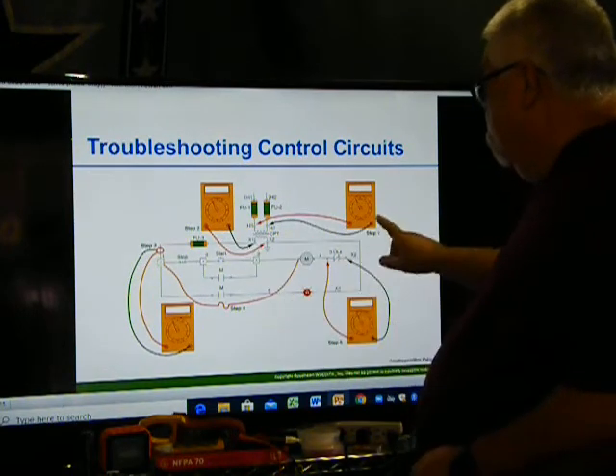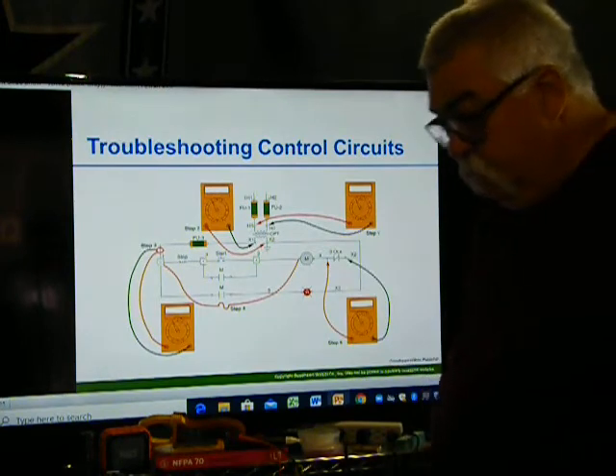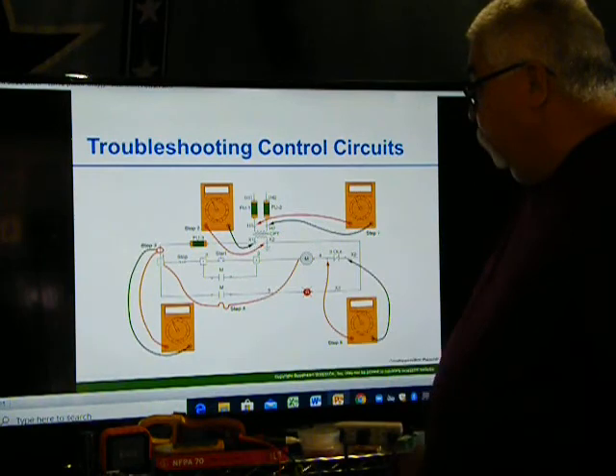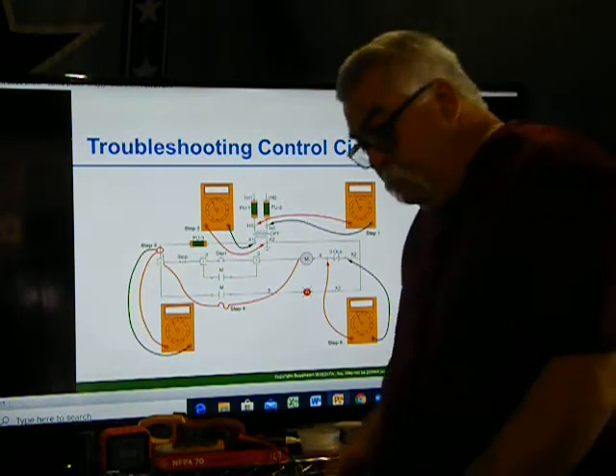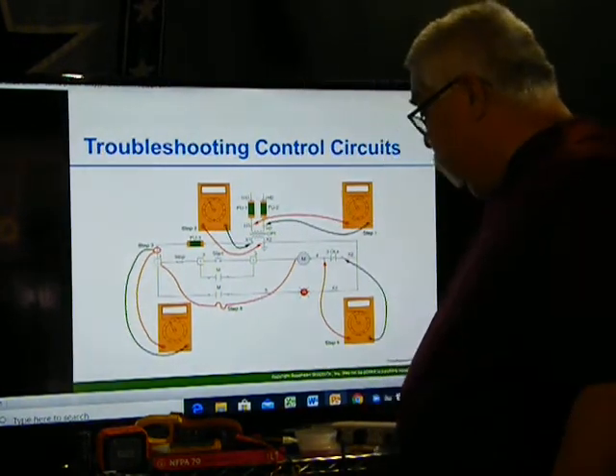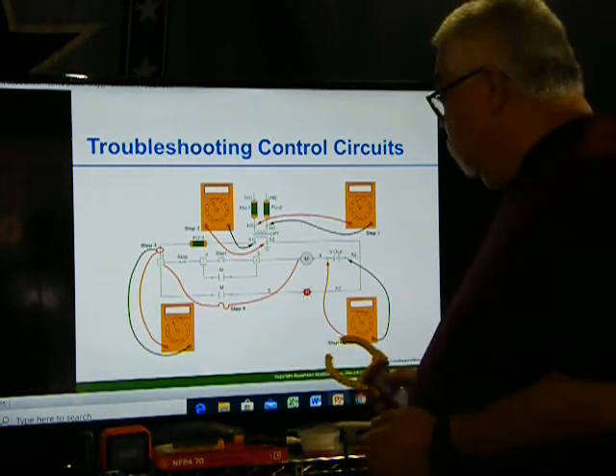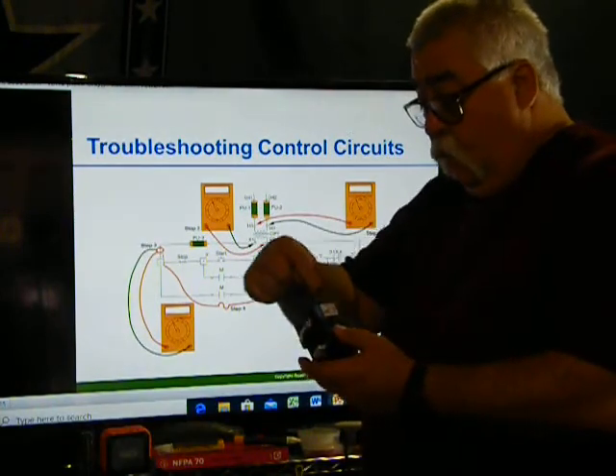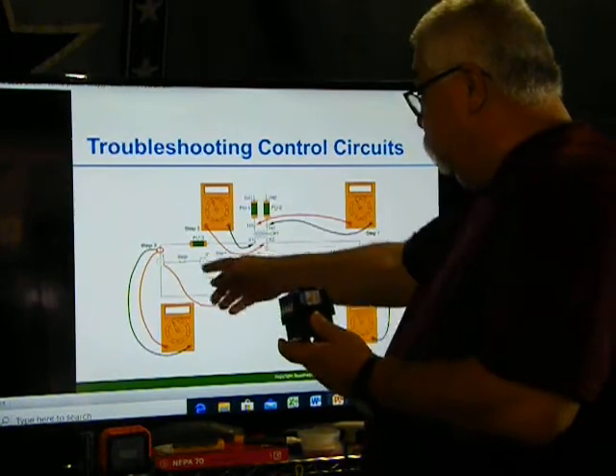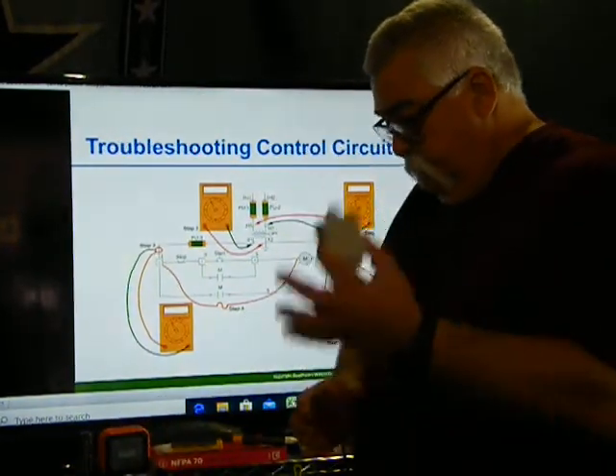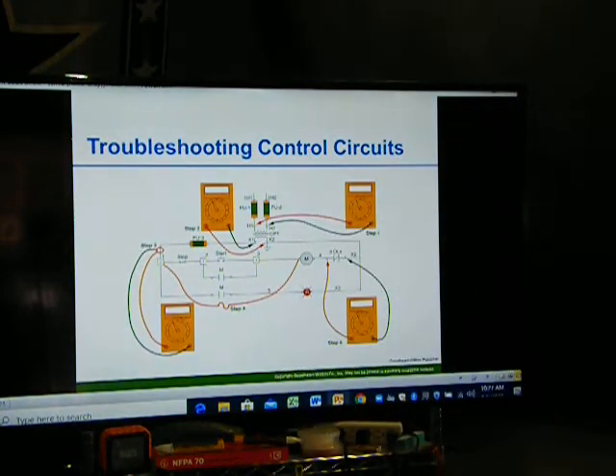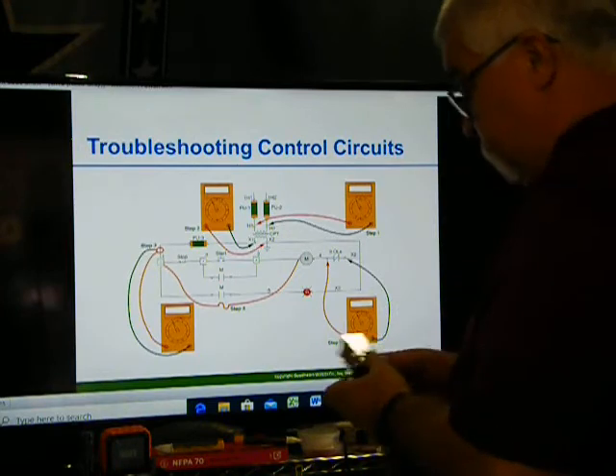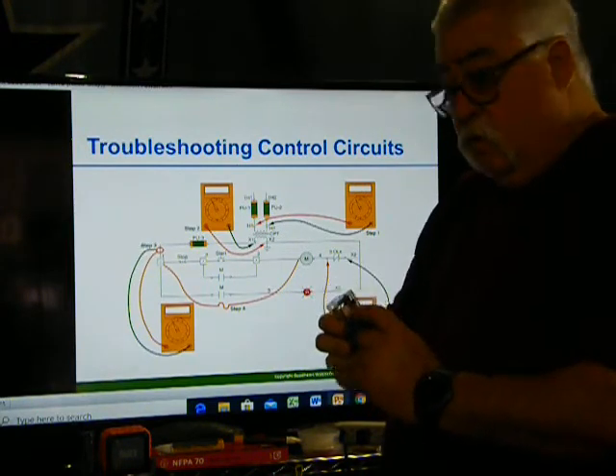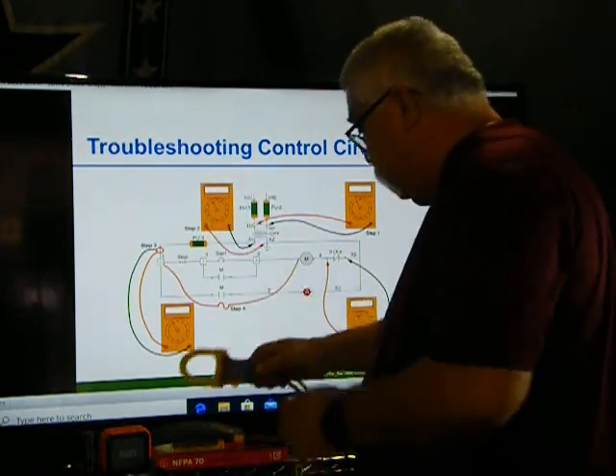Okay, so you want to test. Step 1, check your input voltage. Step 2, check your output voltage. Okay, now they're going to step 3. This says verify the current drawn by the circuit. So if your circuit's working, there is going to be some current because the coil inside of here is going to draw current. Switches don't draw any current, but the coil does, and it's minimal. But you can read it. Whether you got one of these, or one of the little ice cubes, there's a coil inside of it, so this will draw current. So you can get your amp probe, clamp it, and see if it's got current.